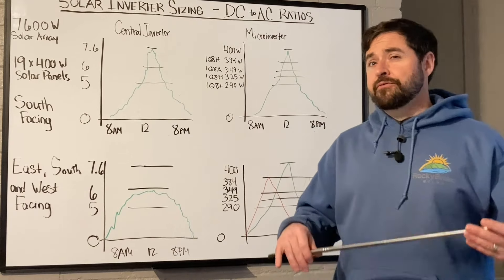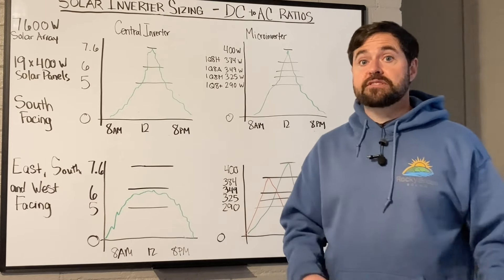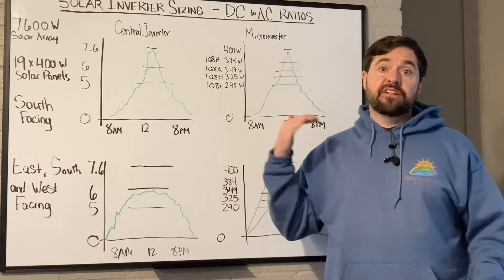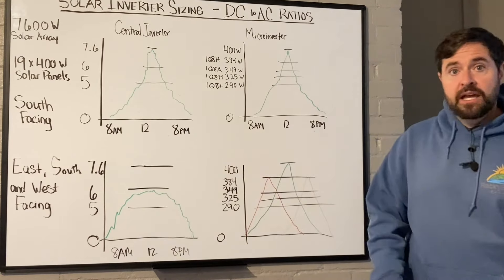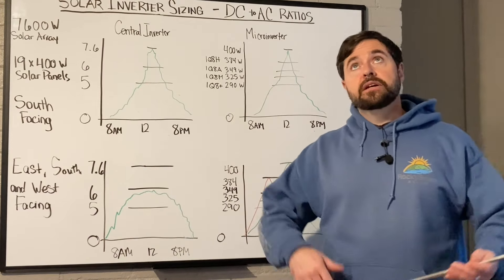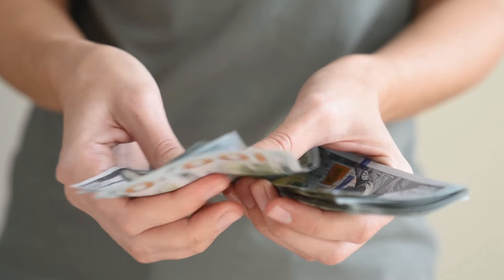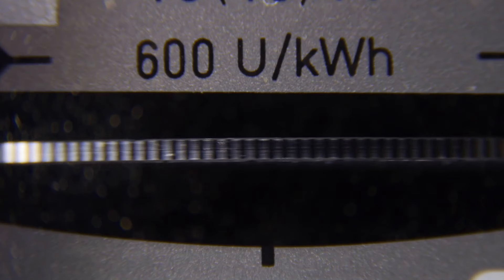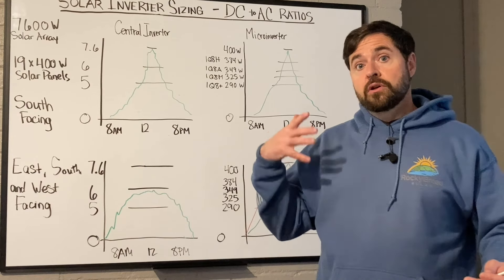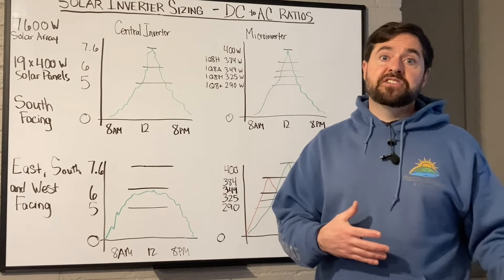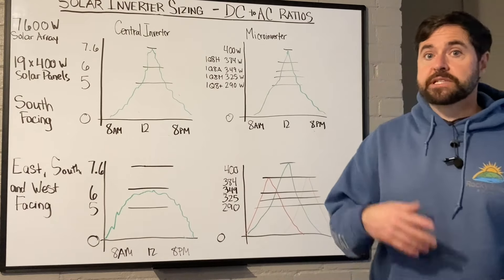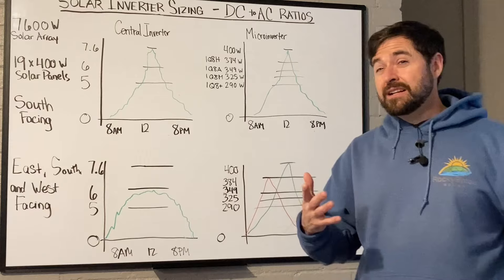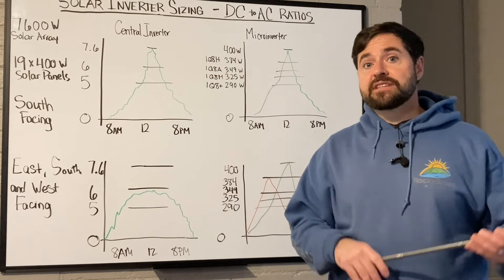After the video, you should be able to make an informed decision on which inverter is the right size for your specific needs. In the solar industry, it's actually really common to have your DC array size be significantly larger than the size of your inverter or the AC size of your system. The reason for that — there are several reasons — but it could be as far as just saving a little bit of cost on your inverter, your wires, your breakers. It could also be because of the configuration of your electrical service. With larger inverters comes larger PV output current, which depending on your situation could mean having to conduct a service upgrade or some expensive electrical work in order to connect a larger inverter to your specific electrical service. So a lot of times, if you can get away with a smaller inverter without much sacrifice, that can be the right choice for you.